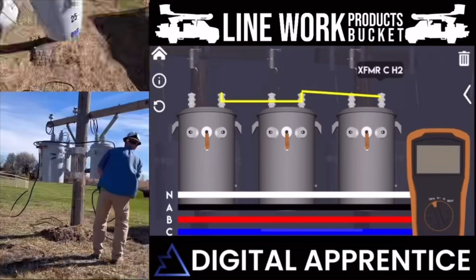So once we start putting these hot legs into these transformers, I'm going to shape them, and I'm going to take them across the neutral, and then I'll shape it down to the center pot. And it just makes everything look nice and clean, and then all your connections are underneath that center transformer. I see a lot of transformer banks out there where they just drop the legs straight into the service connection area, and it works. It's not the way I do it.